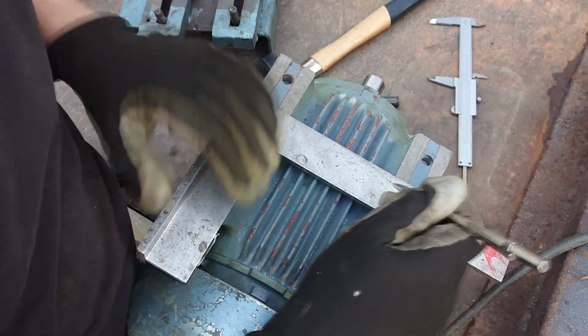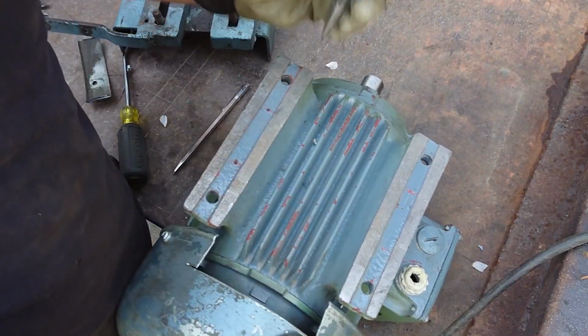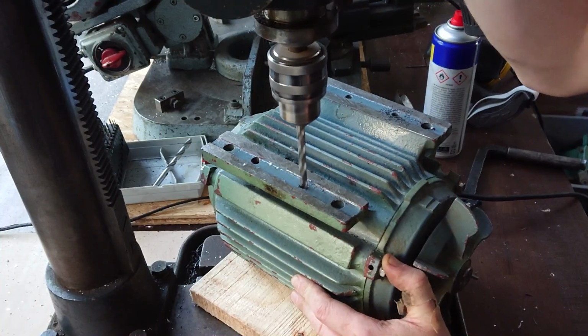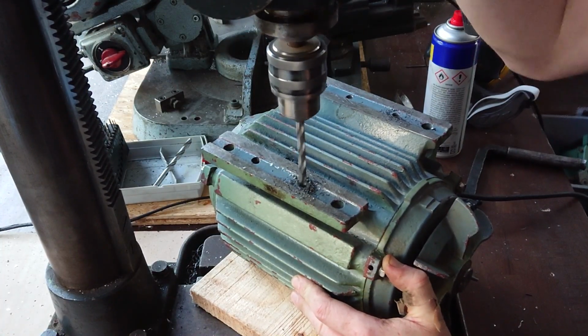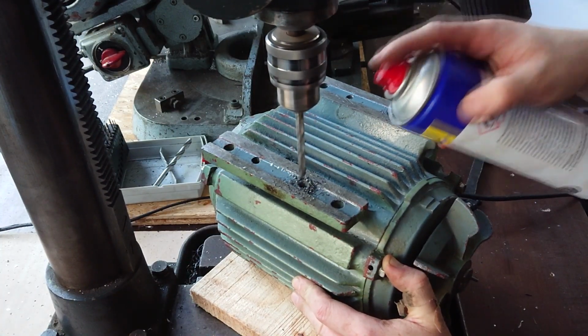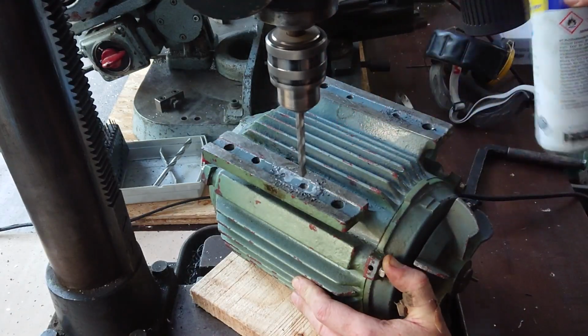Measurements are taken and I punch mark the motor in 4 spots, where new holes are then drilled using the drill press. This is necessary so that the motor shaft will be positioned correctly to accommodate a pulley that aligns with the pulley driving the pump.